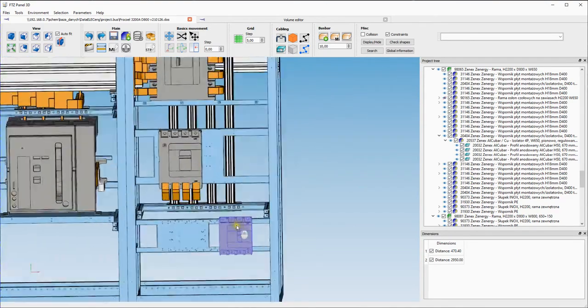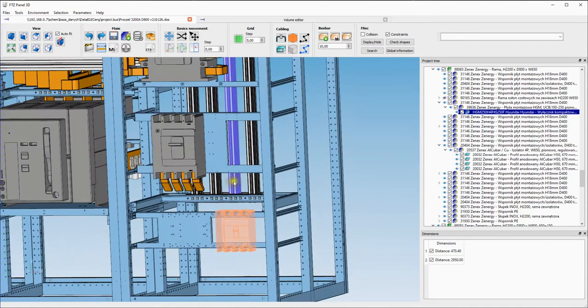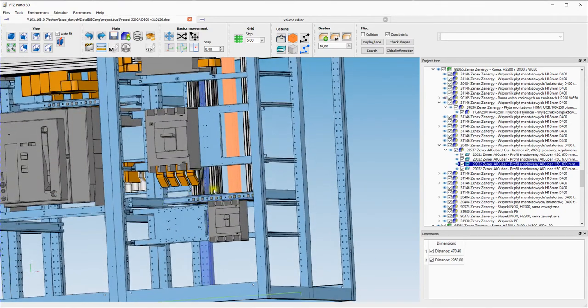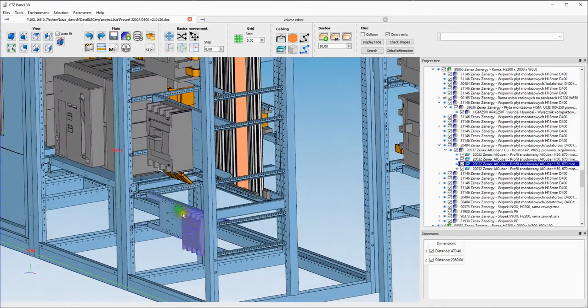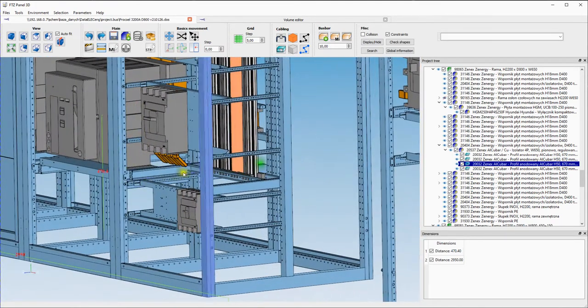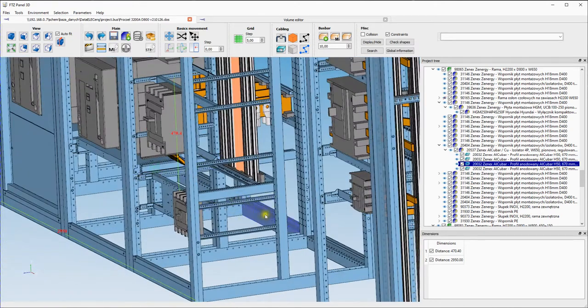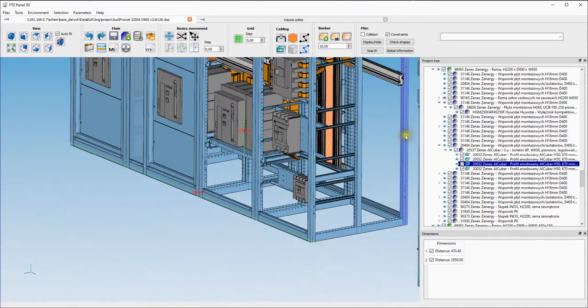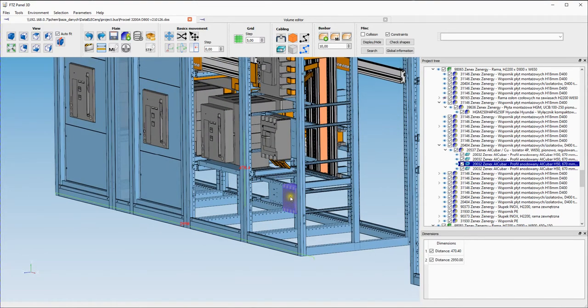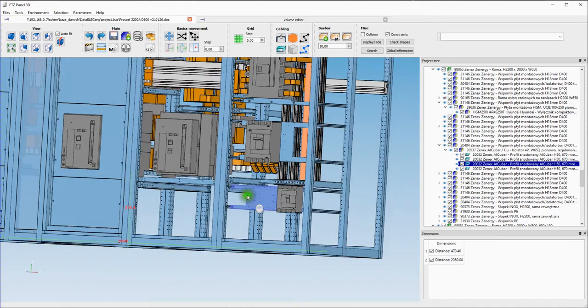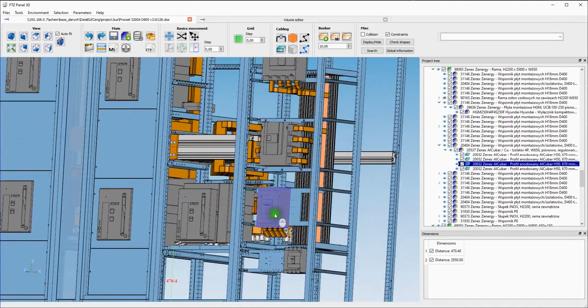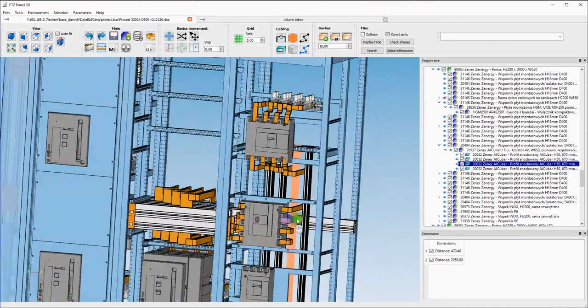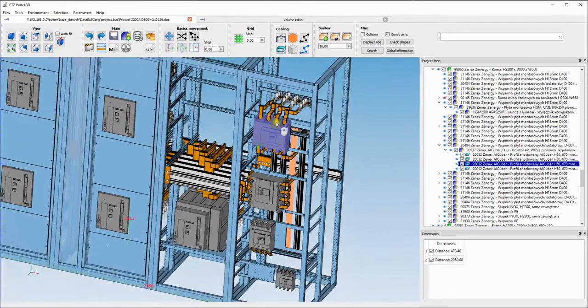As you see, this breaker will have to be connected from the bus bar behind somewhere by cables. So 250 amperes by cables, and outgoing here by cables down. And also you need to imagine here some toroids by the cables, maybe behind the panel, somewhere at the rear. So it's not so easy and nice to connect a toroid here. Also there is no additional space.